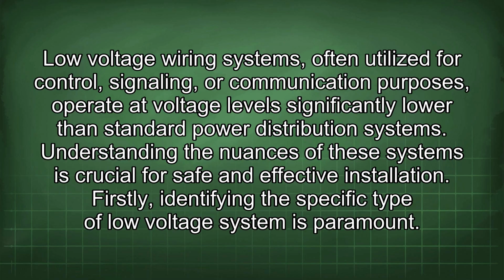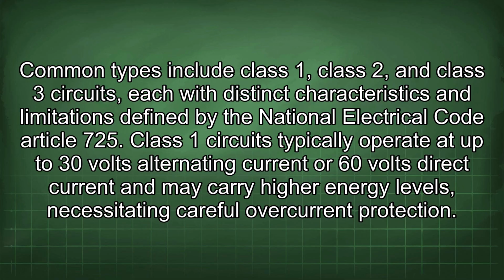Low voltage wiring systems, often utilized for control, signaling, or communication purposes, operate at voltage levels significantly lower than standard power distribution systems. Understanding the nuances of these systems is crucial for safe and effective installation. Firstly, identifying the specific type of low voltage system is paramount. Common types include Class 1, Class 2, and Class 3 circuits, each with distinct characteristics and limitations defined by the National Electrical Code Article 725.